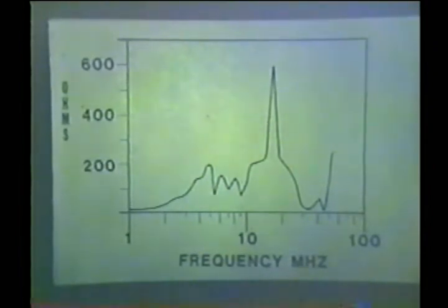The calculated frequency of 4.4 megahertz was measured at 4.6. The calculated value of 5.9 was measured at 6. The calculated value of 8.8 megahertz turned out to be 9, and the calculated value of 17.6 megahertz was actually measured at 17. And indeed, when this machine did develop troubles with extreme contamination of water and rust on both of the end windings, one of the primary frequencies where the EMI occurred was at 17 megahertz.